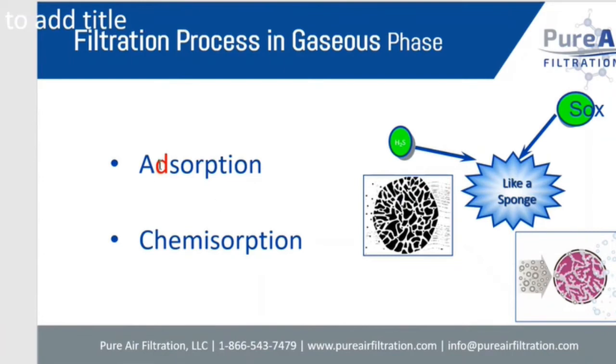Yeah. So this is what activated carbon looks like. If you looked at it under a microscope, actually, this is what it looks like under a microscope, but this is a visual of it. So gases, it uses the principle of adsorption. Gases go into these pockets and they get stuck in there, but they can get unstuck. Chemisorbents are where gases go into the inside and they actually react and turn into a solid on the inside. And typically it's some type of a salt is what the chemical category is. It's non-toxic, non-hazardous. And the beauty of this purple product here is it actually changes colors when it's used up too. So if you use this product in the system, the customer can grab a sample of the adsorbent, look at it, and if it's still purple, then there's still life left in the system. And they can judge how much life is left with the adsorbent system.